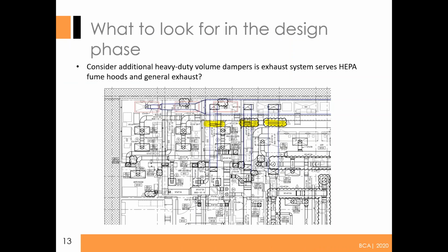And then here, my last slide will be that sometimes you need heavy-duty volume dampers when you have HEPA filters and fume hoods. HEPA filters easily can have an inch of static pressure. Basically, the air won't go through them obviously, and they'll be drawing too heavy from the other rooms. So when you have like a lab, a university, or someplace like that where they're using one exhaust system and drawing from some hoods and drawing from some registers that have no hoods on them or no filters on them.